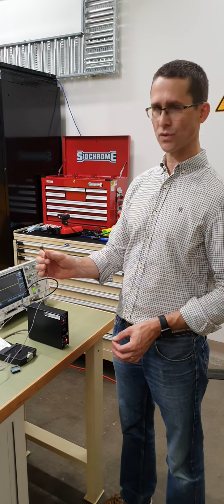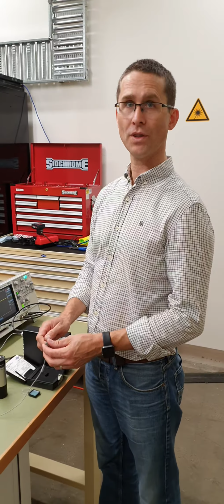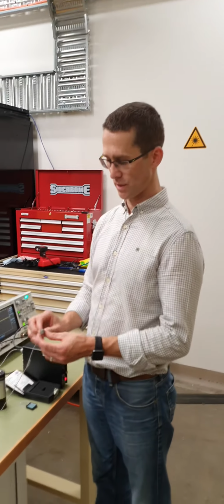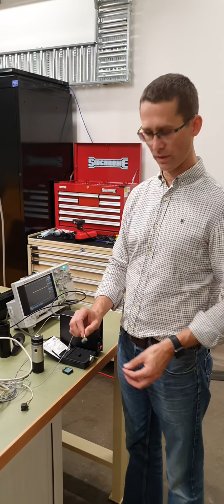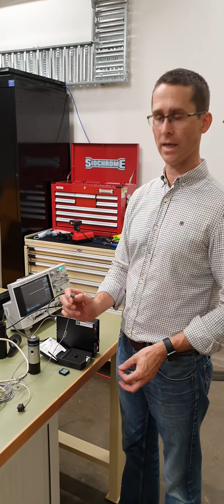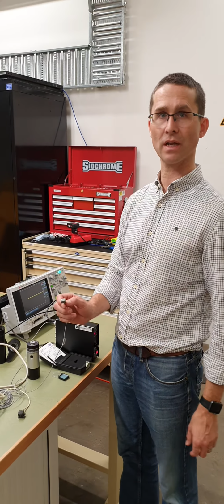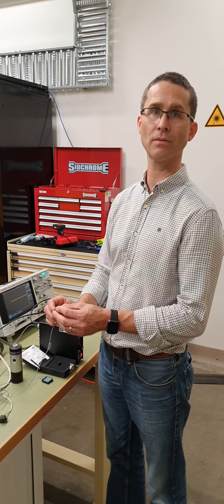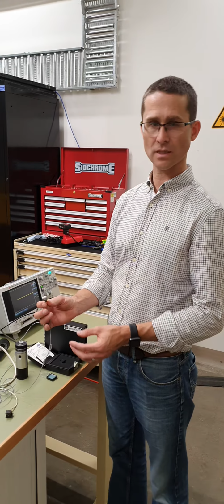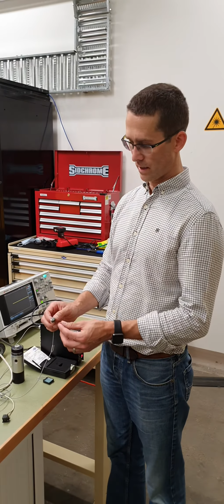So these transducers we have to handle with great care. One thing we must be very careful not to do with these transducers is to drop them, especially onto concrete floors where we can introduce a very high acceleration level into the transducer, which will damage it, probably destroy it. And these sensors are worth thousands of dollars each, literally.